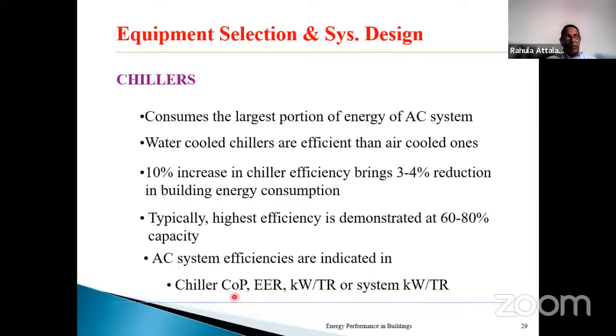Earlier, COP was very dominant. Now it is more kilowatt per ton of refrigeration, that is, kilowatt of electricity use per unit of cooling. So this gives a good indicator of how efficient either the chiller or the entire system is. Typical values for kilowatt per ton of refrigeration may be 0.38, 0.4, and the system kilowatt per ton might be about 0.8 because of the inclusion of the pumps, fans, etc.